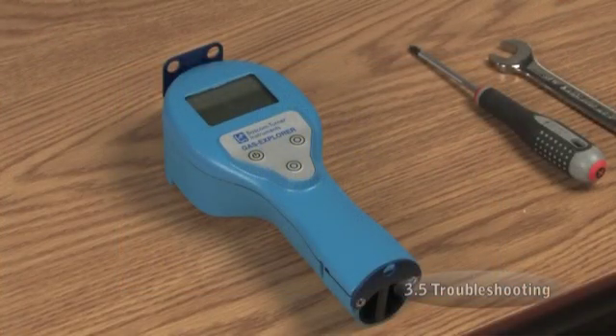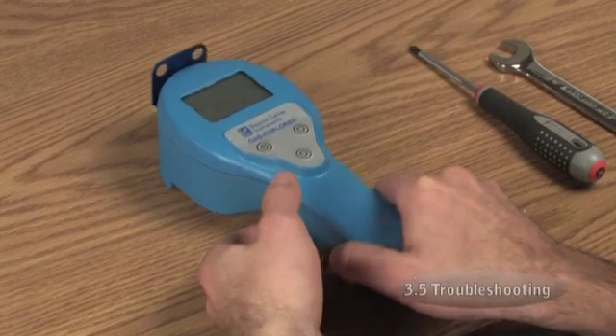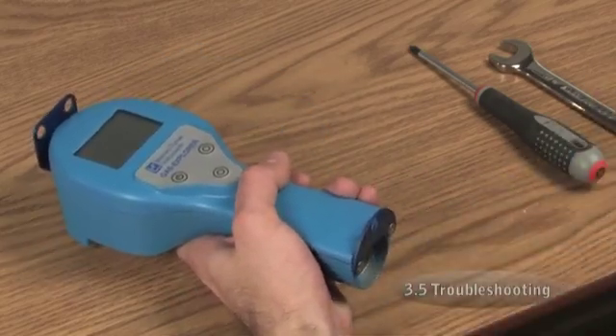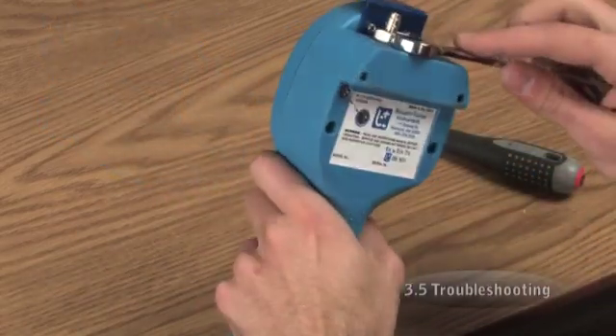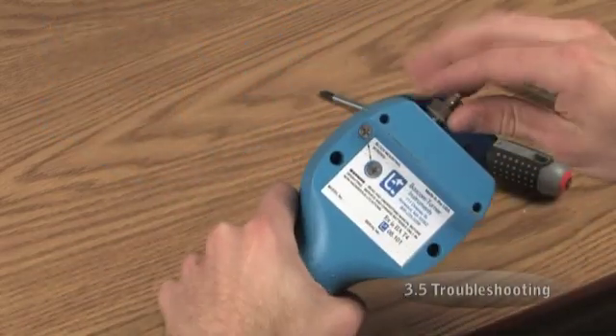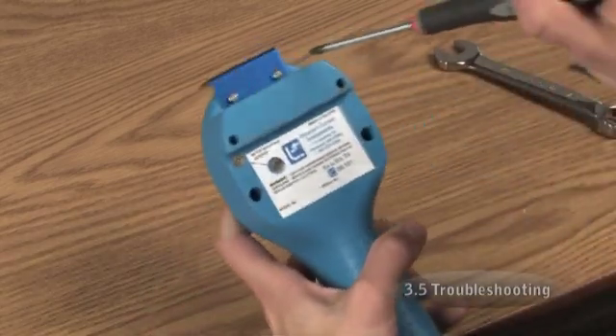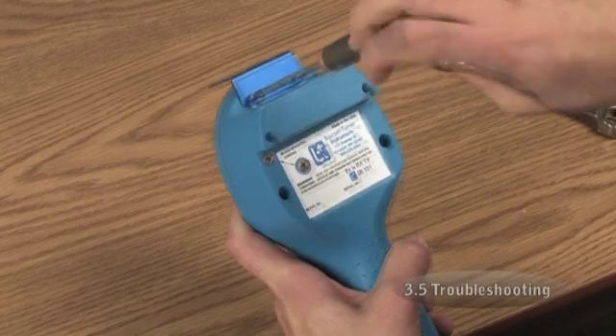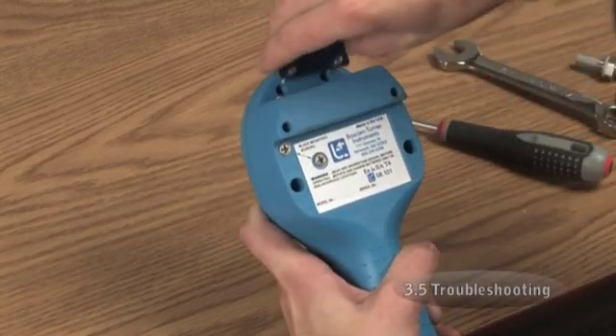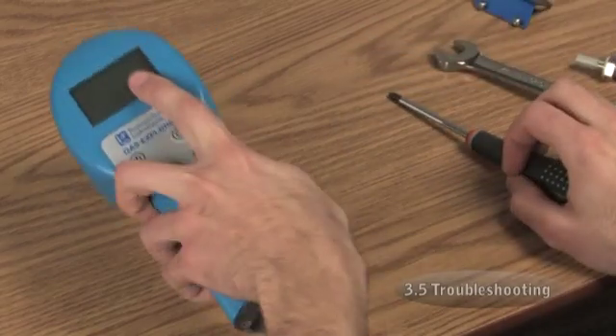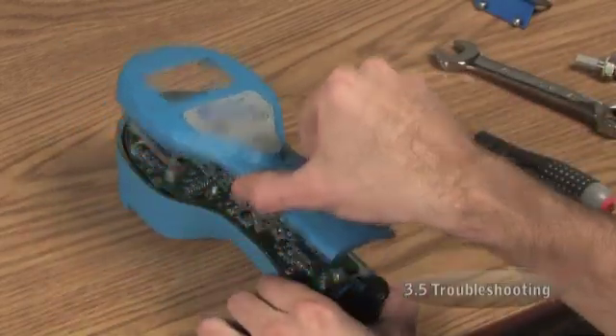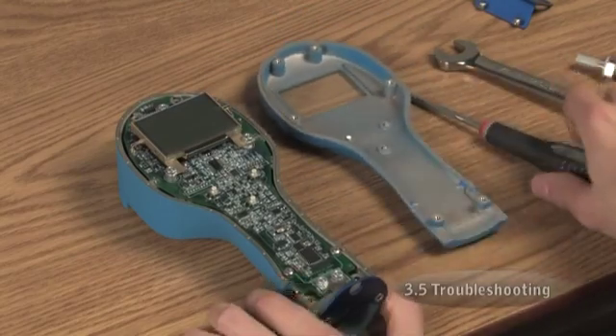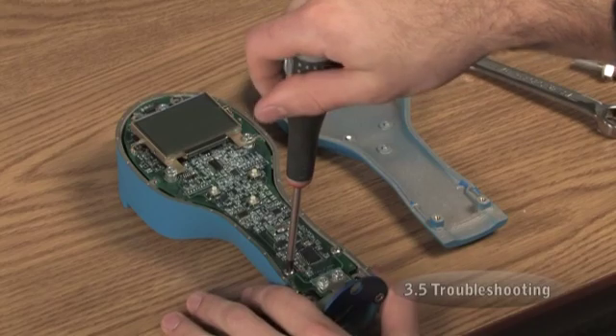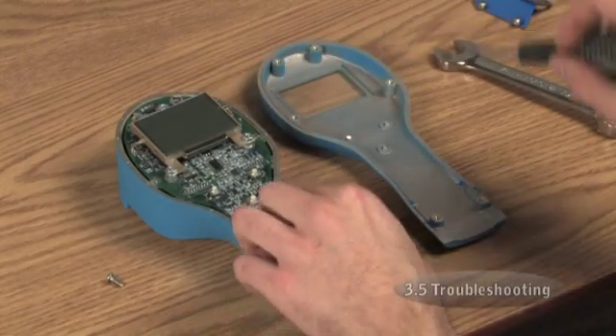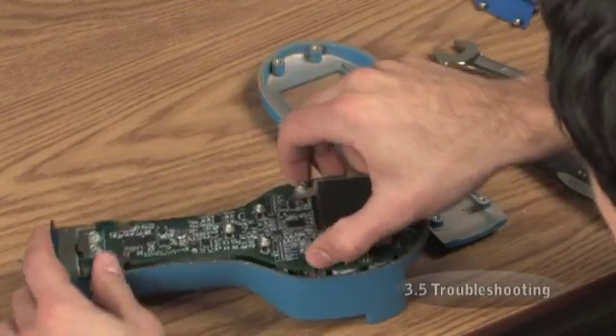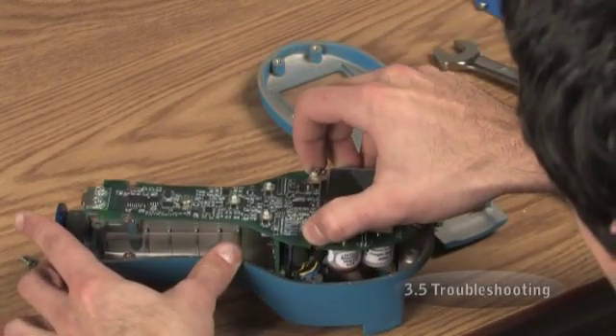To replace any sensor in your Explorer, you will need to do the following. Remove the batteries from the Explorer. Using a 5/8 inch wrench, remove the inlet filter and washer. Remove the 6 Phillips head case screws. Separate the top from the case by gently lifting it. Remove the 2 Phillips head screws holding in the circuit board. Loosen the board by wiggling it slightly, then gently lift it out, taking care not to twist or flex it.